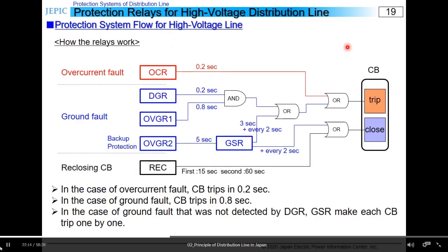This is a figure which shows how the relays of distribution line work. As shown in red, overcurrent of overload or short circuit is detected by OCR, and CB is made to trip in 0.2 seconds after overcurrent detection. Blue shows the protection relays for ground faults. DGR works in 0.2 seconds after it detecting ground fault current, while OVGR works in 0.8 seconds. So, if ground fault goes on for 0.8 seconds, both relays work and CB will be made to trip. If, for example, a spontaneous ground fault like tree touching occurs, CB doesn't trip, but DGR does. In the case like this, we patrol that feeder to prevent power outage.